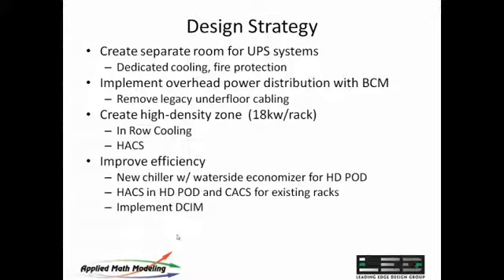In doing all of this, we wanted to improve efficiency. So to support the in-row cooling, we implemented a new chilled water system with new chillers in an N+1 configuration, and added waterside economizers, since there was no free cooling utilized in the data center when we started the project. We believe chilled water was the right decision to support the high-density loads, and it also gives great ability to utilize free cooling.